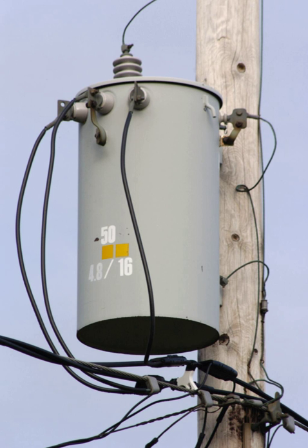Rural services normally try to minimize the number of poles and wires. They use higher voltages than urban distribution, which in turn permits use of galvanized steel wire. The strong steel wire allows for less expensive wide pole spacing. In rural areas, a pole mount transformer may serve only one customer. In New Zealand, Australia, Saskatchewan, Canada, and South Africa, single wire earth return systems (SWER) are used to electrify remote rural areas.